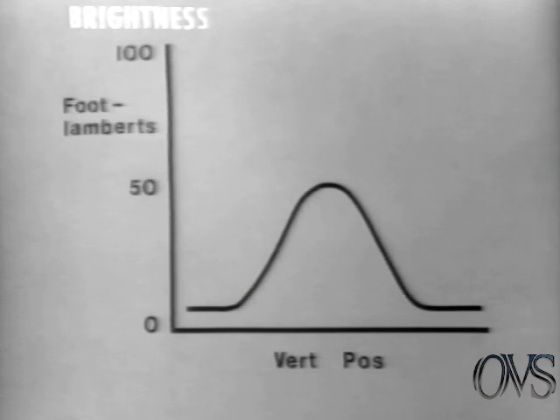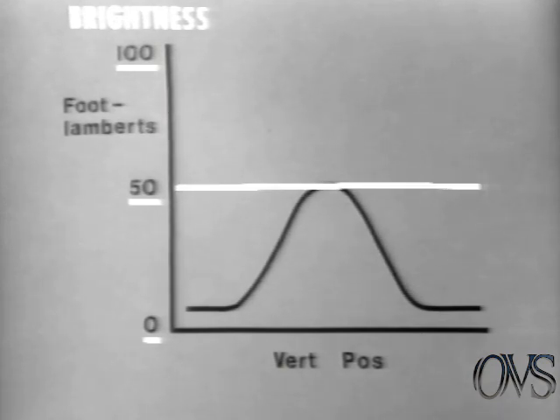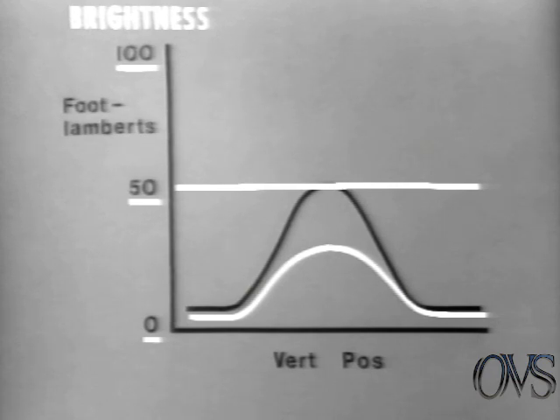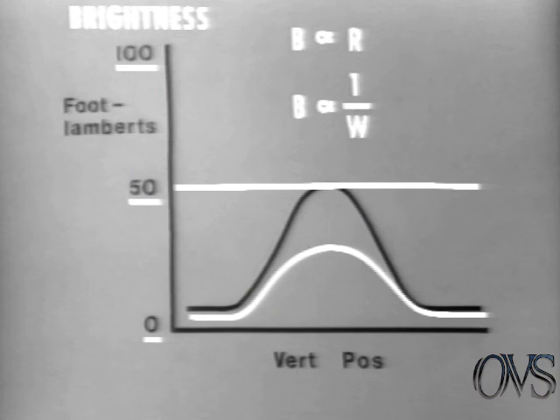Before making the measurement, the graph is calibrated for 0, 50, and 100 foot Lamberts using a standard light cell reference. Hewlett Packard guarantees that this peak, representing maximum brightness, will be at least 50 foot Lamberts. However, if the trace isn't focused correctly, the trace will widen, the curve will flatten out, and the spec may not be met. Since brightness is directly proportional to refresh rate and inversely proportional to writing rate, if either of these factors are changed, the brightness will also change.